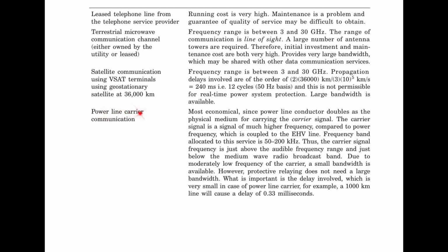However, power line carrier communication is actually the most economical, since the power line conductor doubles as the physical medium for carrying the carrier signal. The carrier signal is a signal of much higher frequency compared to the power frequency, which is coupled to the EHV line. The frequency band allocated to this service is 50 to 200 kilohertz. Thus, the carrier signal frequency is just above the audible frequency range and below the medium wave radio broadcast band.